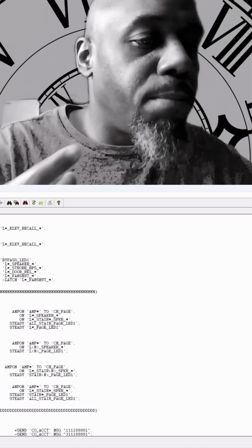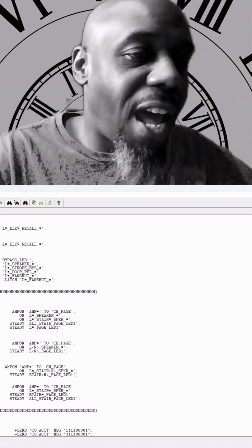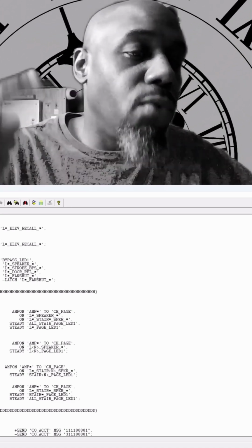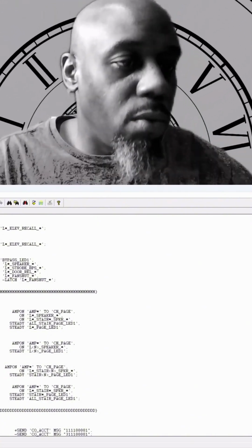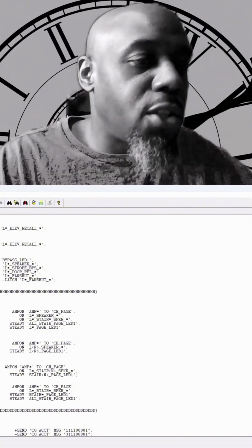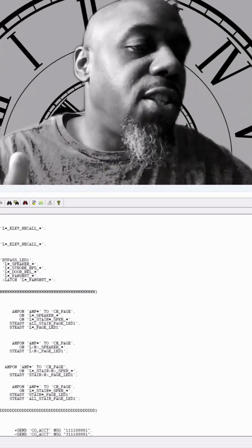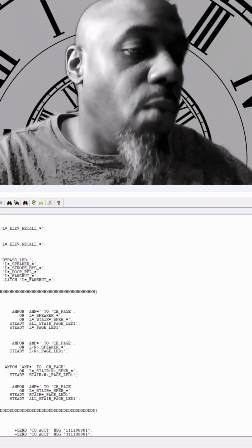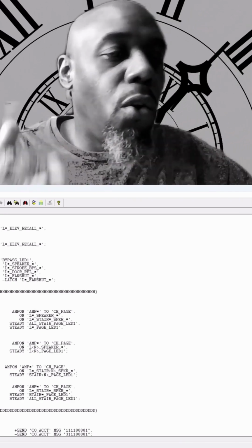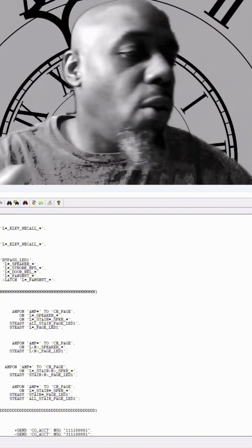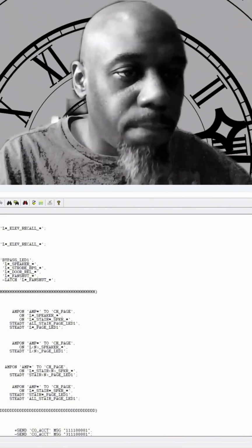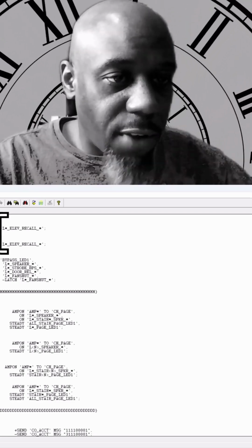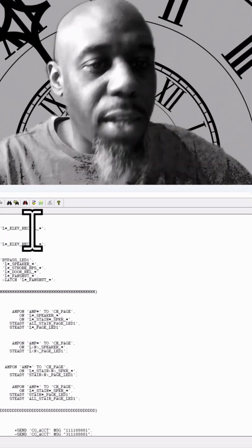These are the syntax that have to be inputted into this rule programming in order for this one particular rule to go true. So these asterisk stars are wildcards. Essentially this is telling me that there is more than one. So it could be L1 auto elevator smoke 1 or something like that. We're going to go to the objects and see exactly what this message label is. And you need this semicolon right here to divide the input statement and the output statement.